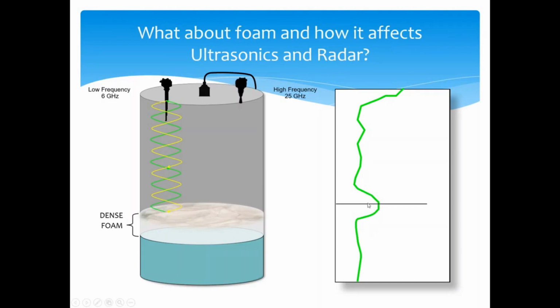Nice high amplitude. One thing to keep in mind though is that the reflection is coming off the top of the foam layer, not the liquid level below it. So we get a good clean signal, but we're not telling you where your liquid level is. We're telling you where the top of your foam is. In a lift station, that's not typically an issue. Foam is only a few, 2, 3, 4, 6 inches, and it's not too big of a deal if we're off by that amount in a lift station application.